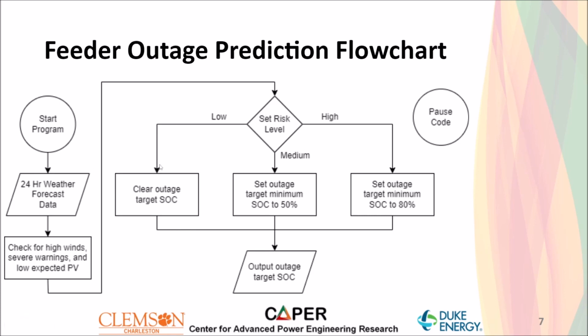A low risk level is going to clear the outage target or let the battery operate in the most economical way. A medium risk will set an outage target minimum to 50%, while a high will set it to 80%. That will finally be output to the peak load shaving algorithm and incorporated into a pre-charged target value ahead of inclement weather.